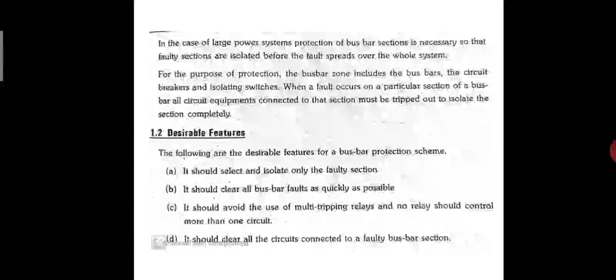Next one, desirable features. The following are the desirable features for a busbar protection scheme. First one, it should select and isolate only the fault section. It should clear all busbar faults as quickly as possible. It should avoid the use of multi-tripping relays, and no relay should control more than one circuit. It should clear all the circuits connected to a fault busbar section.